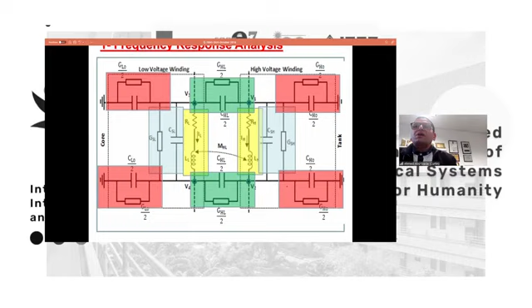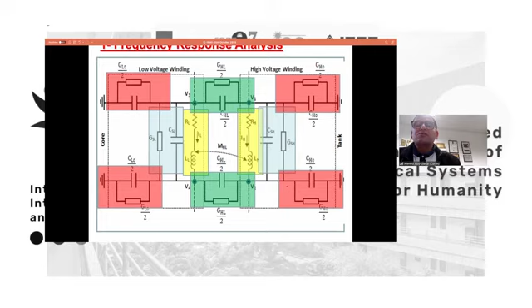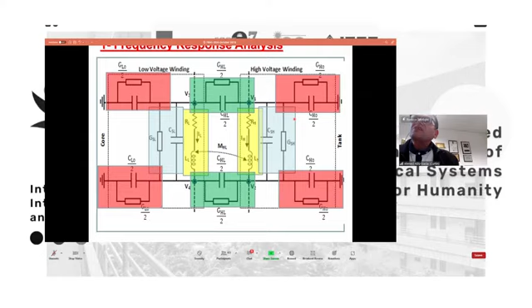We have a capacitive component, we have an inductive component, which are frequency dependent. Remember, XL equals omega L, XC equals 1 over omega C. So any variation in the transformer winding, whether the winding is moving up, down, to the right-hand side, or the left-hand side, due to any reason that I will explain later, will affect the capacitance and the mutual and self-inductance, right? For example, refer to the basic formula for capacitance, epsilon A over D. If you change the distance between two turns, that will change the capacitance, and that will affect the frequency spectrum of the transformer. That's what we call the frequency response analysis signature.